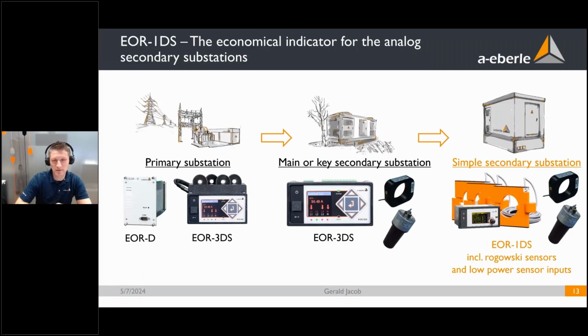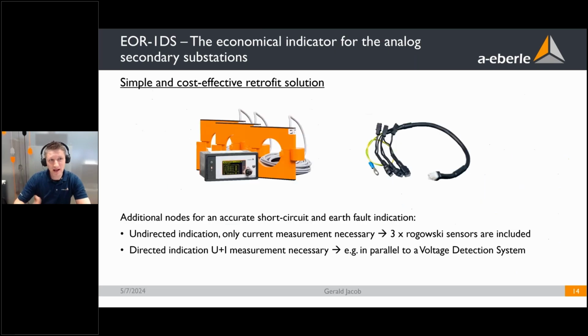As you can see, our devices, of course, can be installed also in primary substations. We also have an EOR-D for primary substations, and the EOR-3DS, for example, is also capable of the requirements in primary substations. But we focus, especially the EOR-3DS, on these main or key secondary substations, so digital secondary substations, and the EOR-1DS is the device for simple secondary substations. This device is a simple and cost-effective retrofit solution.